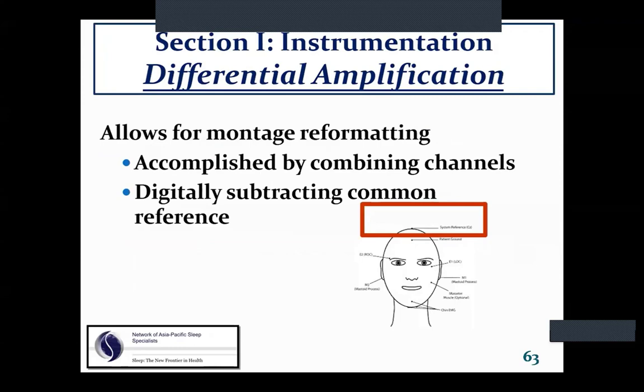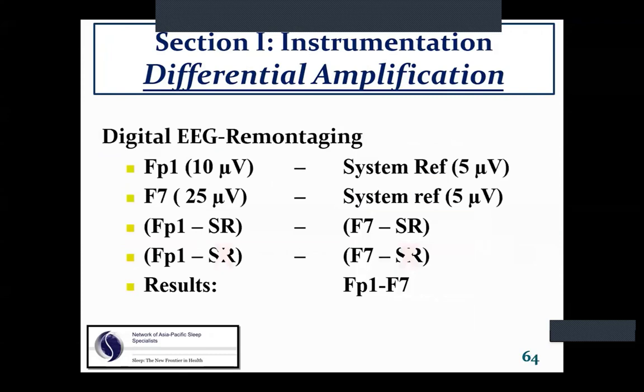And the advantage of a system reference is it allows for montage reformatting. So I can look at my waveforms in a different montage, and it's accomplished by combining channels. Where exactly you place that reference is irrelevant because it's digitally subtracted in the process of differential amplification. So differential amplification, again, is recorded in the system ref montage. So let's say FP1 to system ref, F7 to system ref. And then on the hard drive, not on the screen, we don't ever run the system reference montage on the screen, but on the hard drive, it allows you to save that combination. So why system reference is irrelevant is SR minus SR leaves us with just the two active channels that we wish to record from.